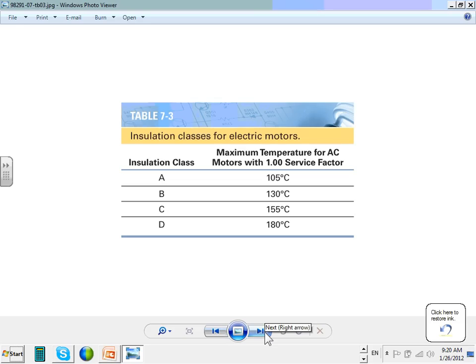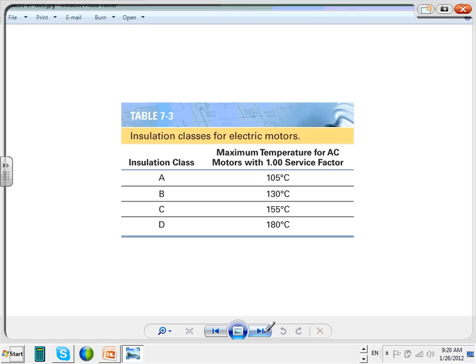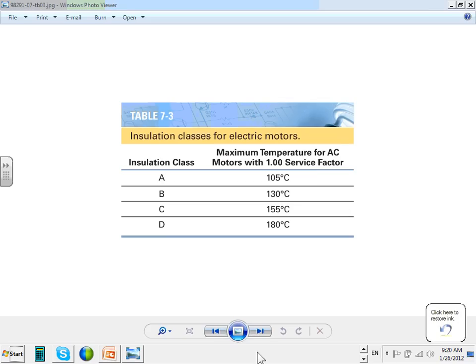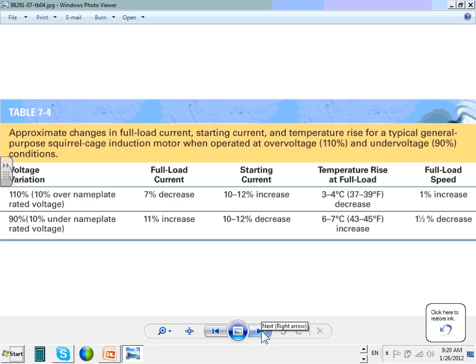Motors, guys, have an insulation level. Remember that, Chris, the windings that got burned? That showed you the windings. These have insulation levels that go from A all the way to D. If you have a level of D, this means, look at this, anybody can handle 180 degrees Celsius? You can get 180 degrees Celsius inside the guts of a motor before the motor starts frying. Anyway, just remember, insulation level B, typical. So you have an insulation level for the magnet wire inside the stator, with a temperature rating that, if you exceed it because of a short circuit, ground fault, or overload, this will trip.